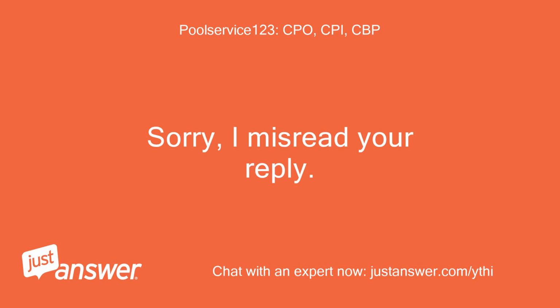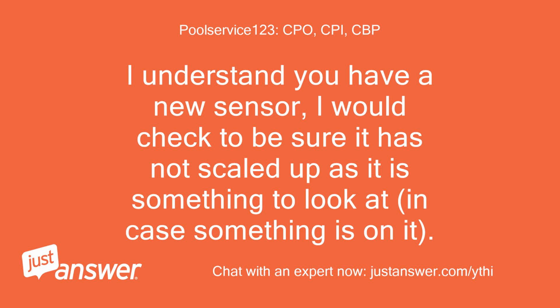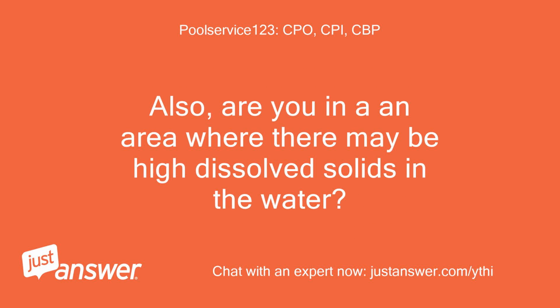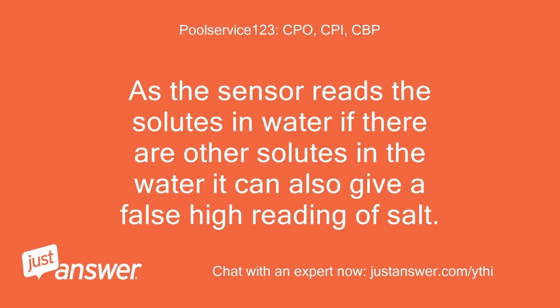Sorry, I misread your reply. I understand you have a new sensor. I would check to be sure it has not scaled up, as it is something to look at in case something is on it. Also, are you in an area where there may be high dissolved solids in the water? As the sensor reads the solutes in water, if there are other solutes in the water, it can also give a false high reading of salt.